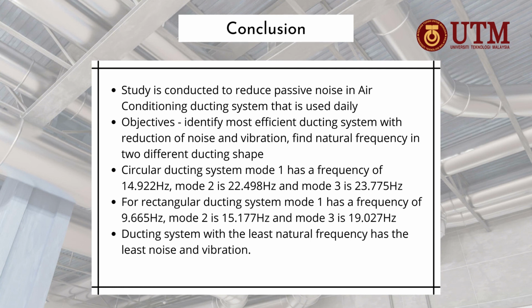Next is to find the natural frequency for the two different ducting shapes. There are more than 9 modes to be obtained. However, only 3 modes are needed to justify which shape of ducting system has the least natural frequency. For the circular ducting system, mode 1 has a frequency of 14.922 Hz, the second is 22.498 Hz, and mode 3 is 23.775 Hz. And for the rectangular ducting system, mode 1 has a frequency of 9.665 Hz, mode 2 is 15.177 Hz, and mode 3 is 19.027 Hz.